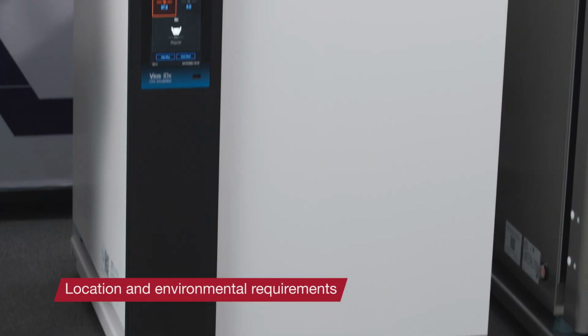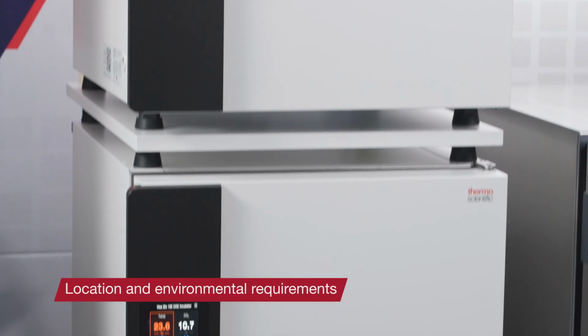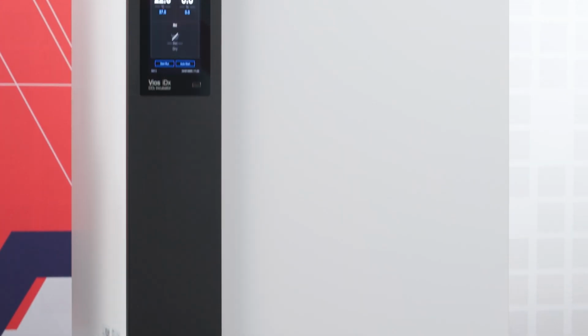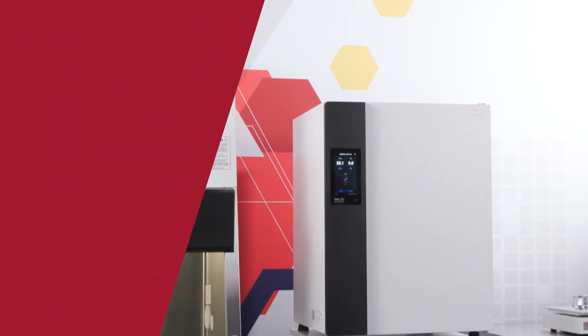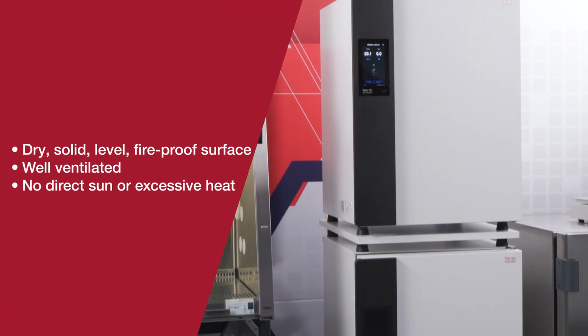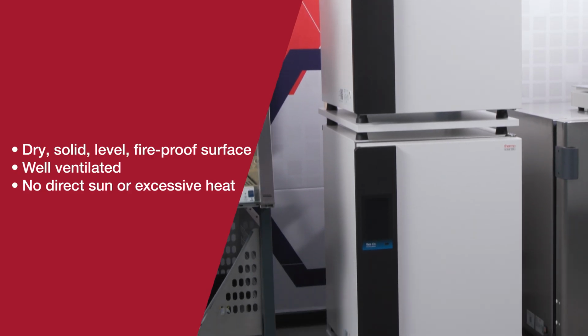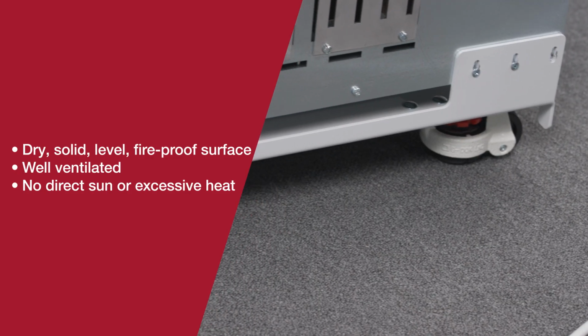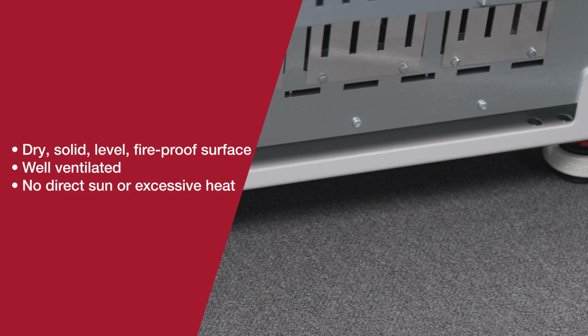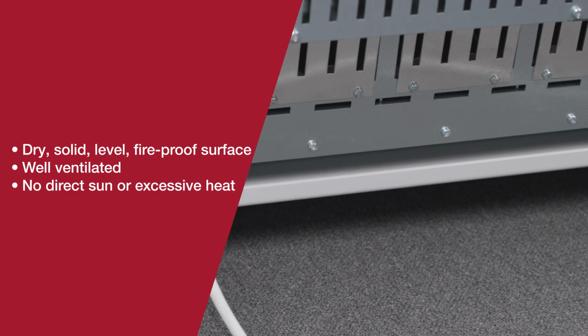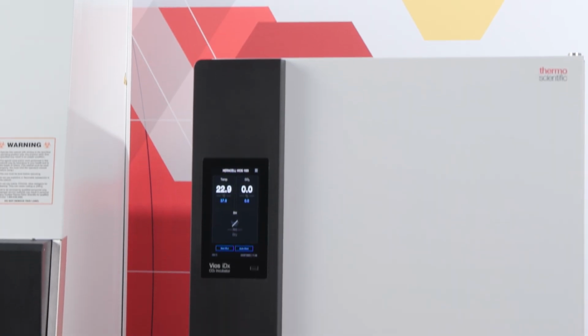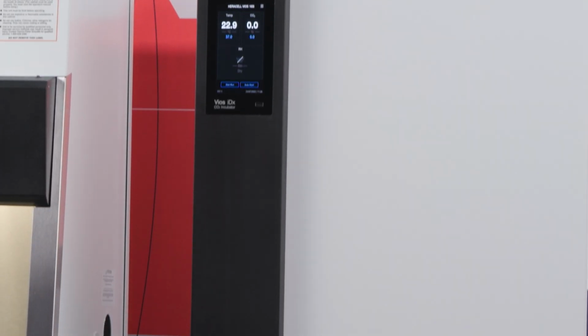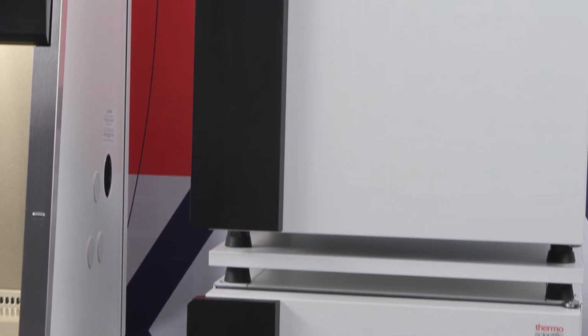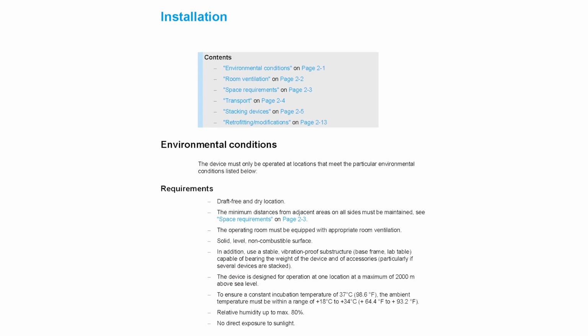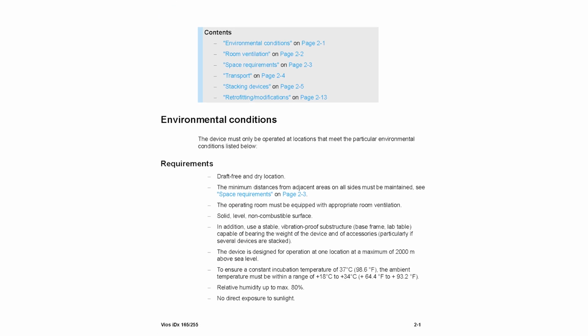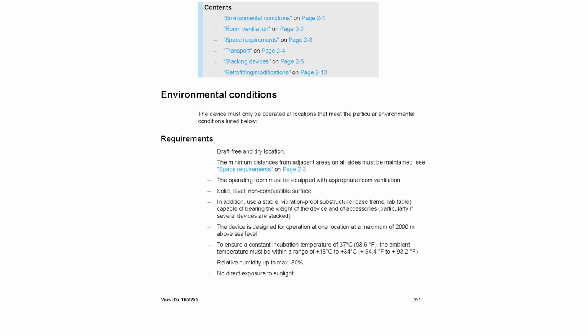It's important to make sure your incubator's installation meets location requirements and particular environmental conditions. Choose a dry, draft-free location with appropriate ventilation, and place the incubator on a solid, level, fireproof surface. Don't expose it to direct sunlight or devices that produce excessive heat. And make sure that the minimum distance to adjacent surfaces is observed on all surfaces of the incubator. Refer to the space requirements section of the operating instructions for more information.